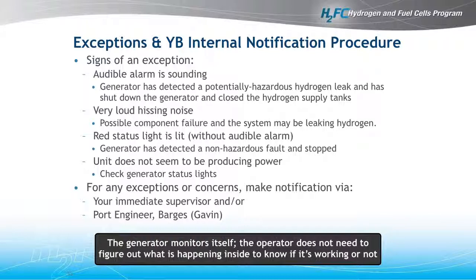The red light, if the status is lit but it has no alarm, then the generator has detected something's wrong, but it's not necessarily a hazardous condition, but it will have stopped. And if the unit doesn't seem to be producing power, then check those generator status lights. For any exceptions or concerns for the Young Brothers folks using this, please make notification via your immediate supervisor and the port engineer for barges. The highlight here is that basically the generator is constantly monitoring itself. And really, there's no need for an operator to have to enter the generator room or do anything besides check that little user panel.